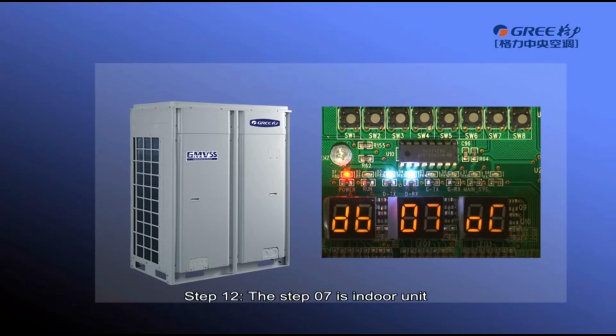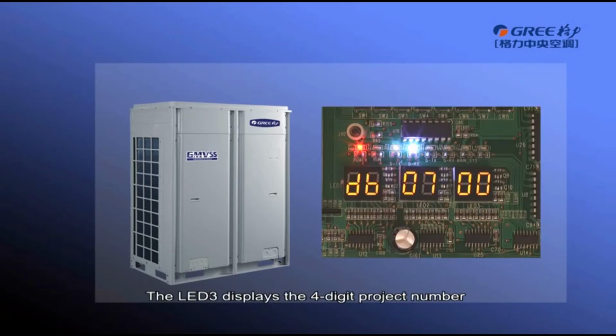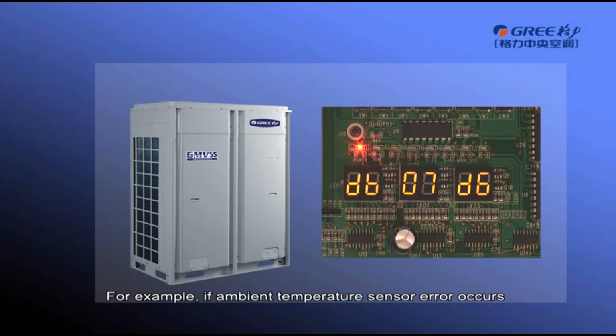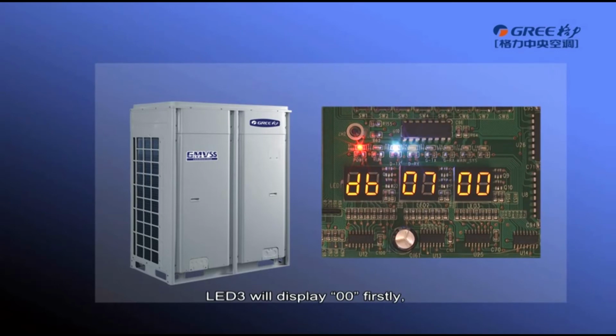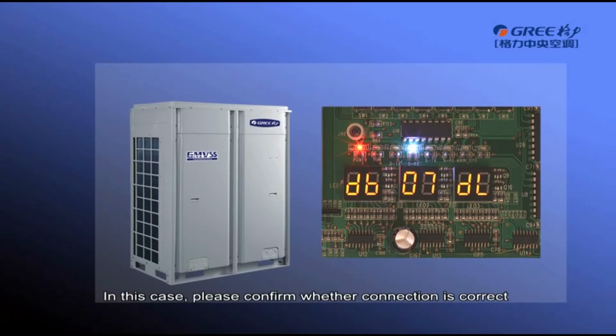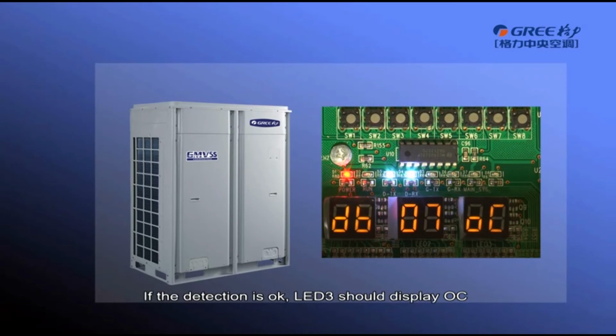Step 7 is indoor unit electric component detection. If the detection is abnormal, the unit retains the current status. The LED 3 displays the 4-digit project number of the faulty indoor unit, and the corresponding error code will be displayed after 3 seconds. For example, if an ambient temperature sensor error occurs in indoor unit number 16, LED 3 will display 00 firstly, then display 16 and display error code DL. In this case, please confirm whether connection is correct, or replace the sensor until error disappears. If the detection is okay, LED 3 should display OC and the unit enters step 8 automatically.